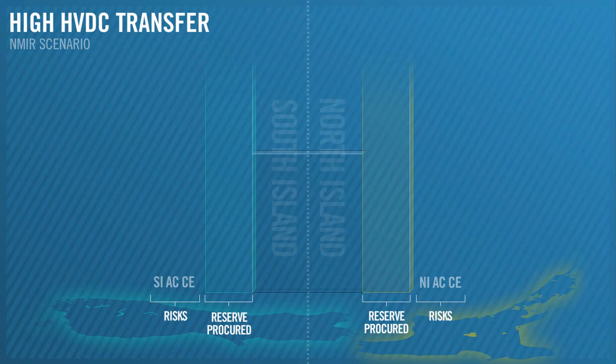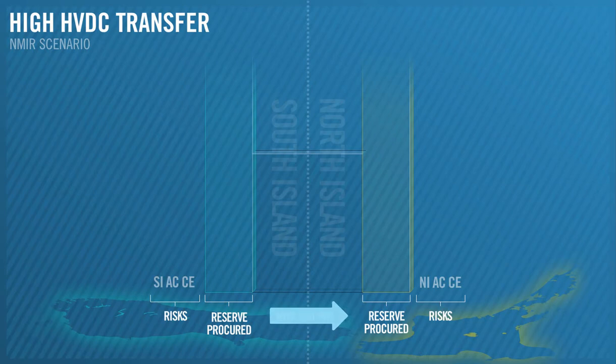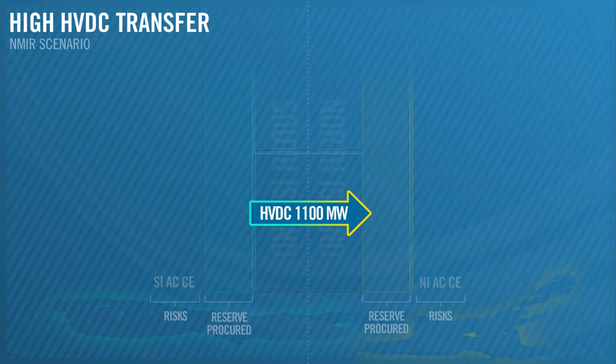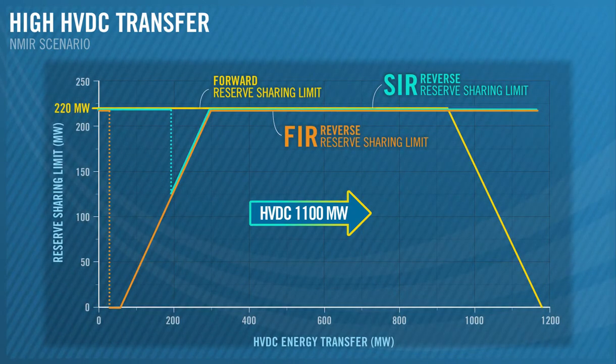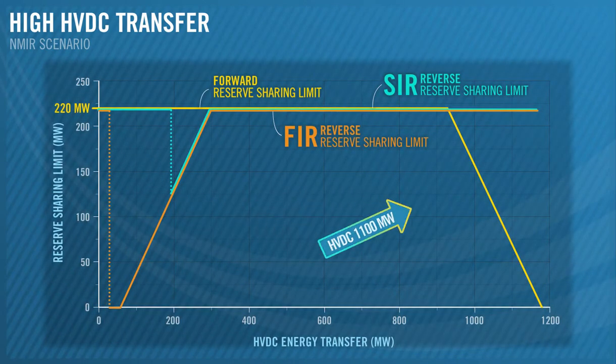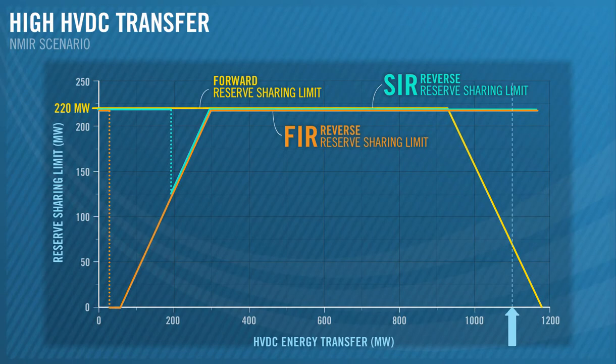Let's look at a scenario where the DC energy transfer is high. The HVDC is set to transfer north at 1100 megawatts. Let's see the effect it has on the forward and reverse reserve sharing limits. The reverse reserve sharing limit is still 220 megawatts, but the forward reserve sharing limit has lowered to 70 megawatts.